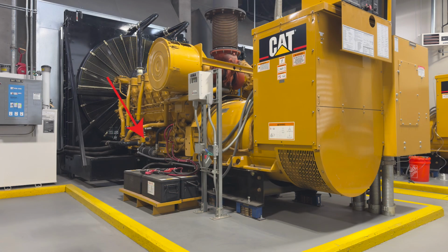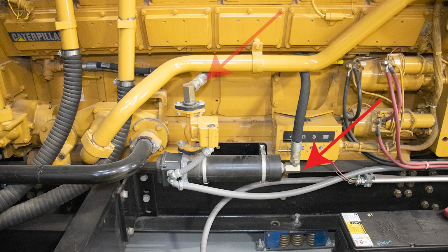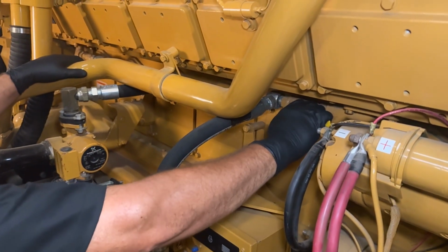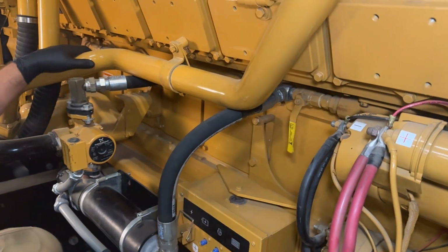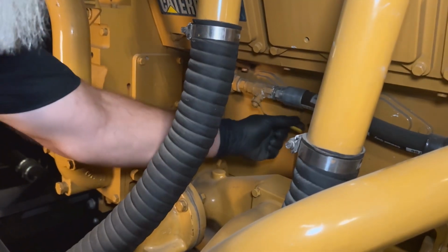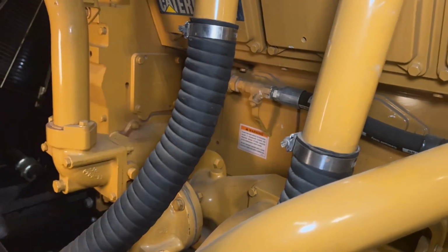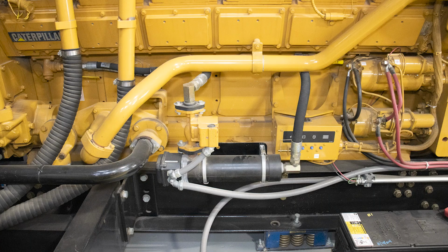Locate the existing engine heater on the generator skid and identify the inlet and outlet connections. The coolant in port on the HE will be connected to the engine block, and the coolant out port will connect to the existing block heater. If isolation valves are installed on the engine, close them before performing any service. If isolation valves are not present, the engine's coolant system will need to be completely drained.